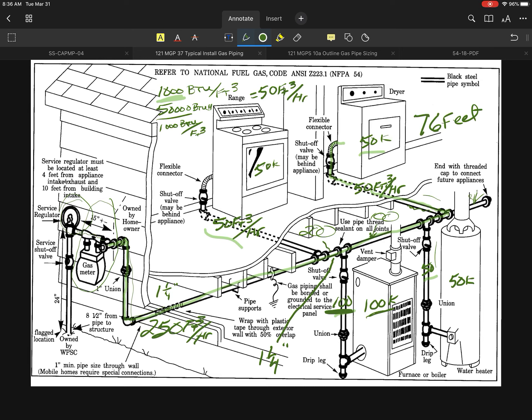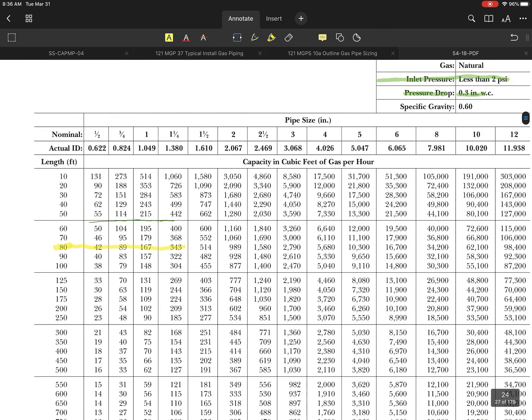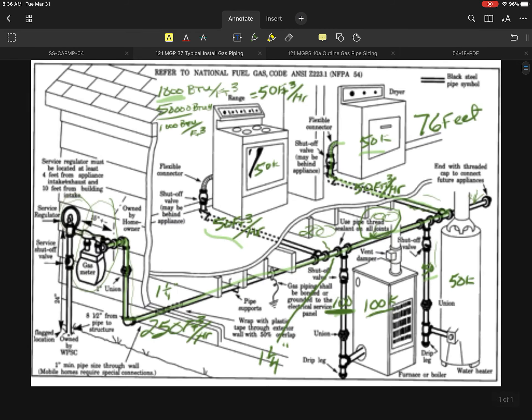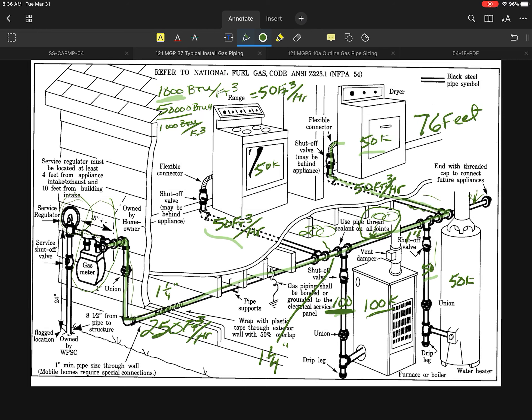Now we're getting rid of a big one—we get rid of 100 cubic feet of fuel to that boiler down here. What's left is the 100. Let's go back to the table. In this case, we're definitely down at a 1 inch line there, because a 1 inch line can handle 167. The 3/4 inch would be too small; it would only allow you 89. So we're going to go with a 1 inch line in the next section.